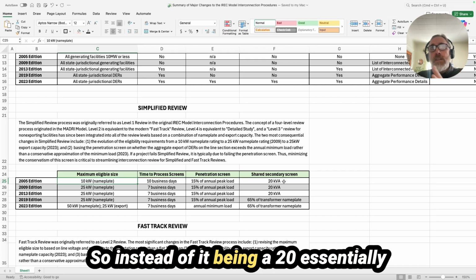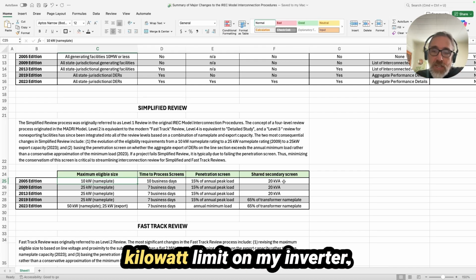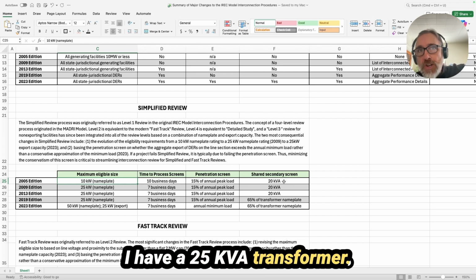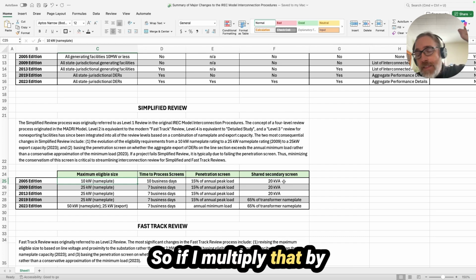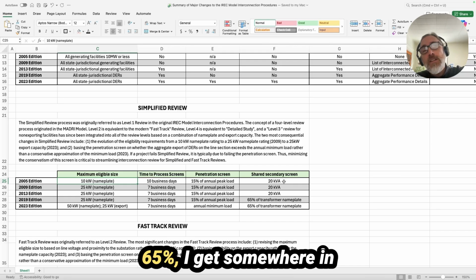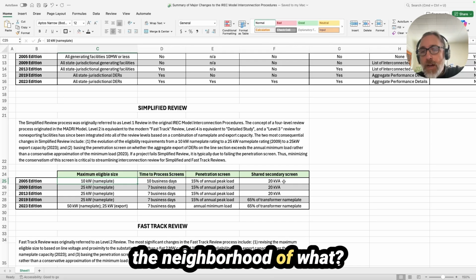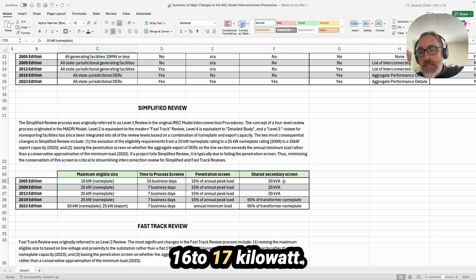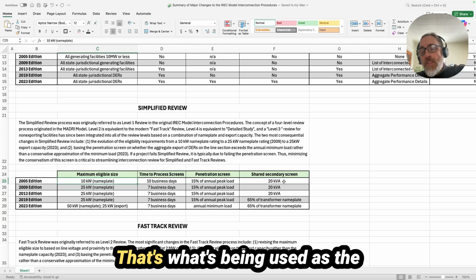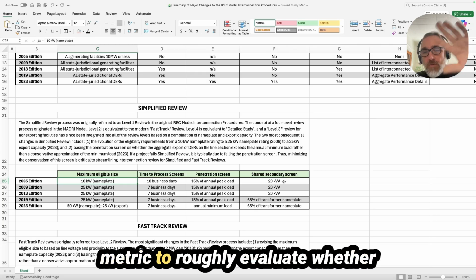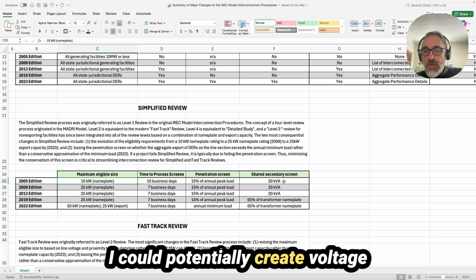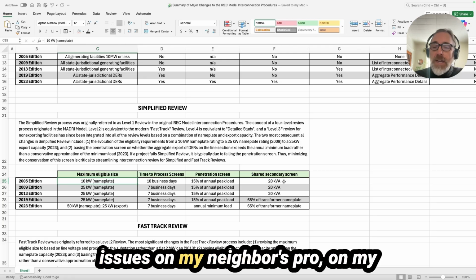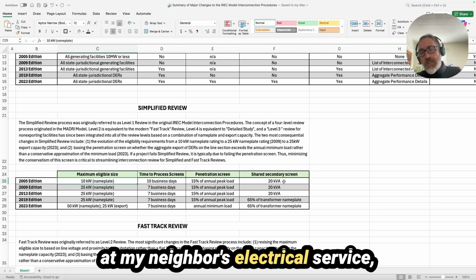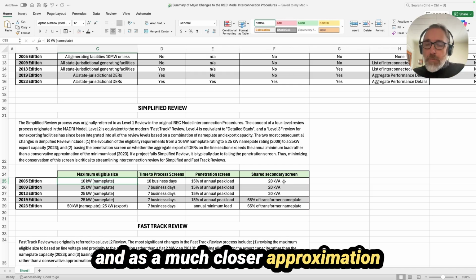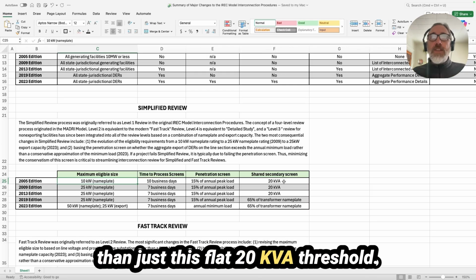So instead of it being a 20 essentially kilowatt limit on my inverter, I have a 25 kVA transformer. So if I multiply that by 65%, I get somewhere in the neighborhood of 16, 17 kilowatts. So that's what's being used as the metric to roughly evaluate whether I could potentially create voltage issues at my neighbor's electrical service, and is a much closer approximation than just this flat 20 kVA threshold.